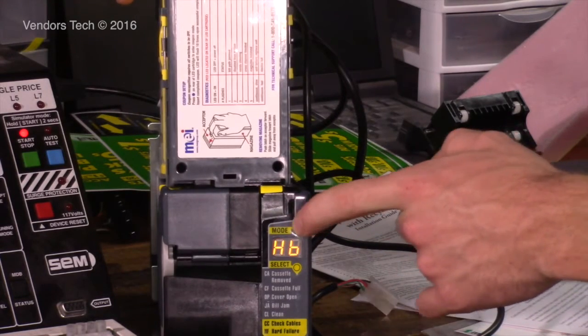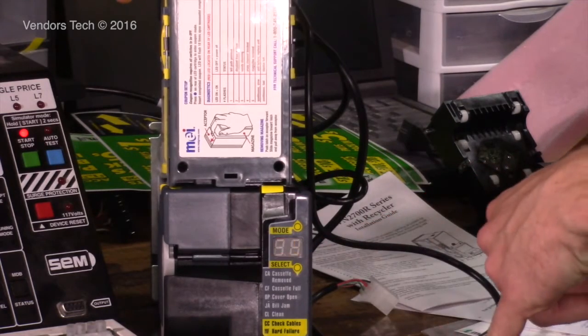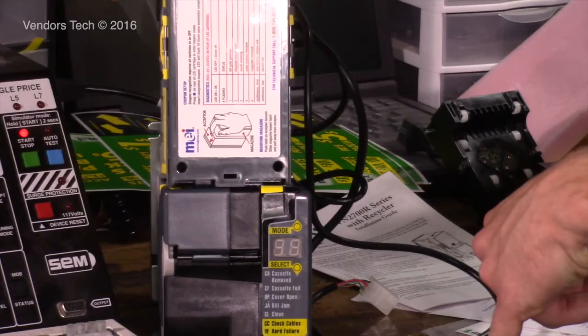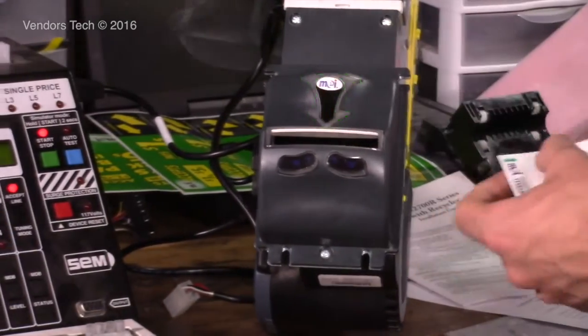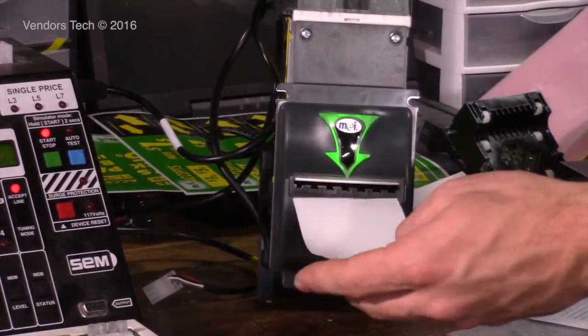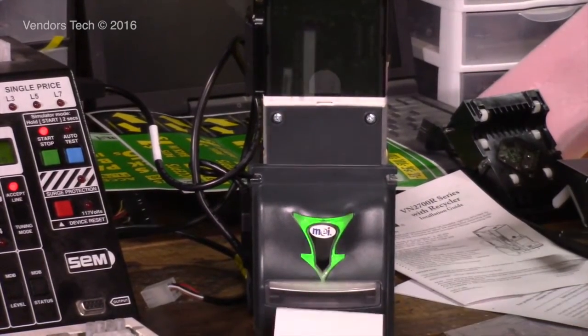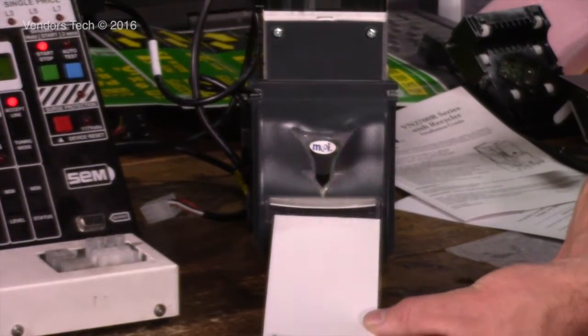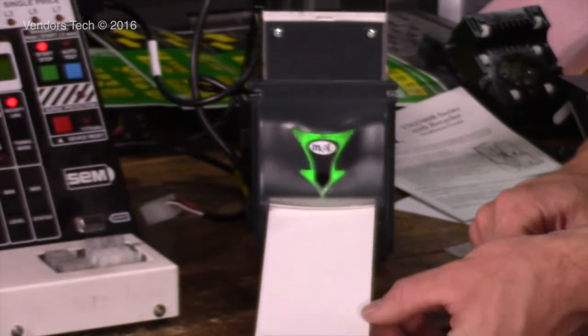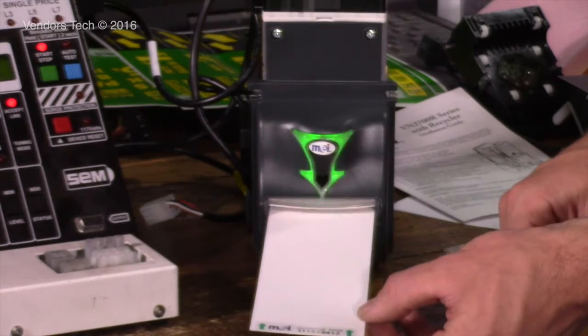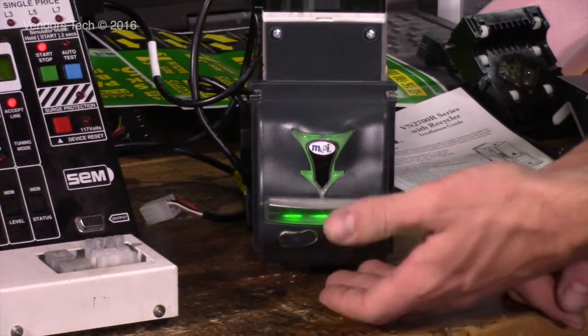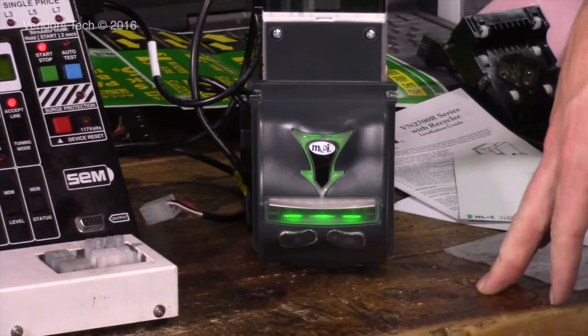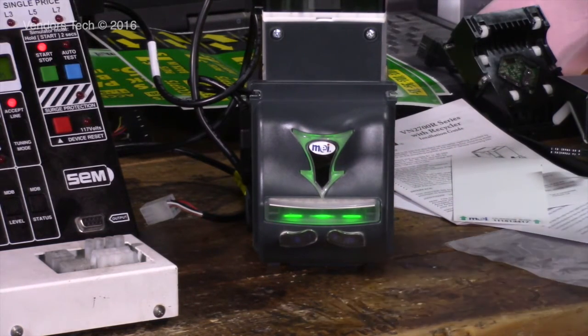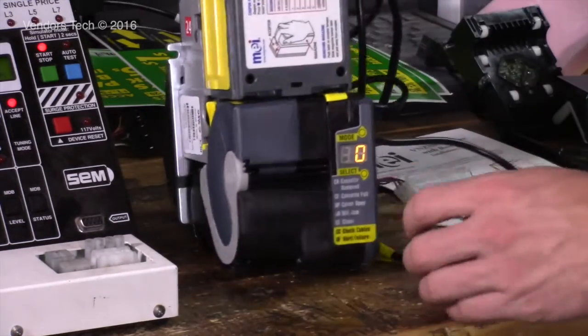All right, so for calibration, we're going to go all the way to the end. PR, hit select once. It's going to say CL. Hit select again. That puts it into calibration mode. We're going to take our calibration paper, and your lights will be flashing. If you have a card reader on the front, you can look in there, and your green lights will be flashing really fast. But you're going to insert your calibration paper, just like I have it here. Green arrows pointing forward on the right side up. Your label on the back of the calibration paper. It's going to take it in and then spit it back out in sections. Be ready to catch it when it comes out. And then give it a few seconds. It's going to restart. It's going to go back to 0.